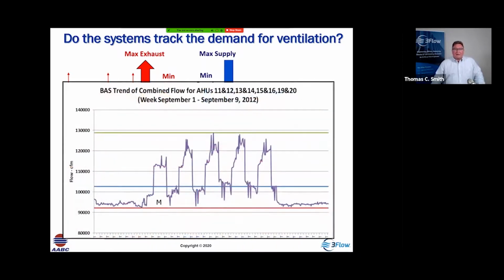So if we look at this and we're to plot it, if we looked at some plot over time, this is a week, Monday, Tuesday, Wednesday, Thursday, Friday, we see that the systems are in fact modulating to meet changes in demand in the spaces. So this would be a properly operating system. We can determine the minimum and maximum flow. I can't tell you how many buildings I've been to, and I ask them, what's the minimum flow when you're in unoccupied mode or all sashes are closed? And nobody knows. Who collects this data?